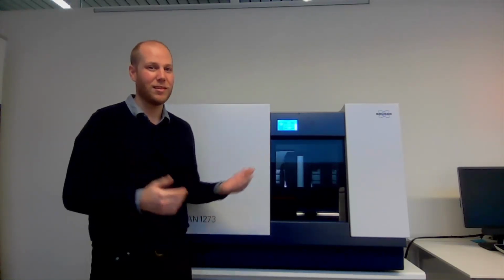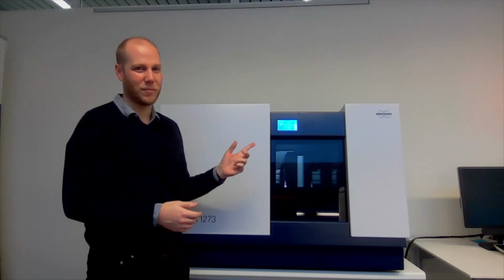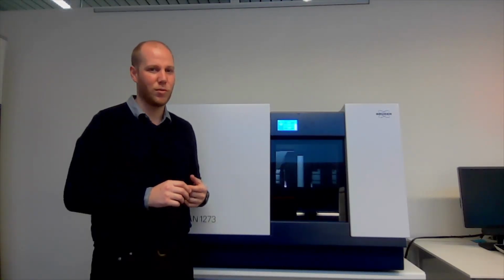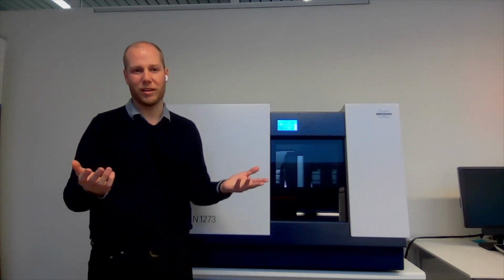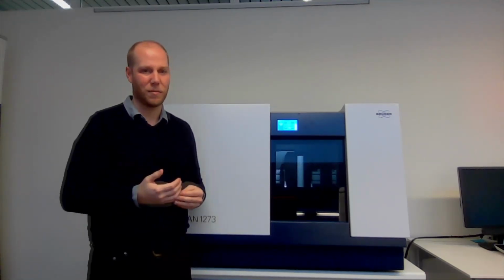As you can see behind me, the Skyscan 1273 is a desktop system. However, do not be fooled by its size. This system packs a mighty punch. The Skyscan 1273 is equipped with a sealed, maintenance-free X-ray source with a maximum power of 39 watts at 130 kilovolts. Capturing these high-energy photons is a high-resolution 6-megapixel flat panel CMOS detector. The advantage of this detector is that it has a large field of view and allows for fast image acquisition times with a good signal-to-noise ratio, creating high-quality images and datasets.